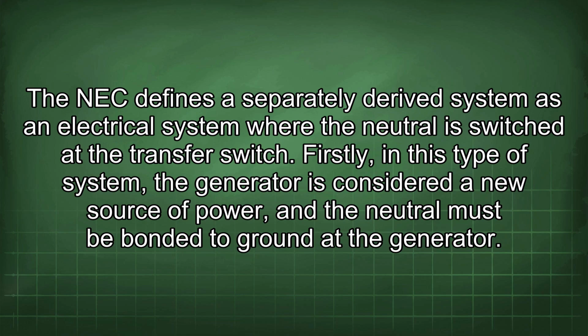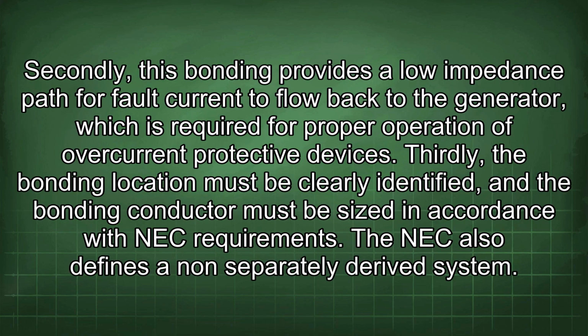The NEC defines a separately derived system as an electrical system where the neutral is switched at the transfer switch. Firstly, in this type of system, the generator is considered a new source of power, and the neutral must be bonded to ground at the generator. Secondly, this bonding provides a low impedance path for fault current to flow back to the generator, which is required for proper operation of overcurrent protective devices. Thirdly, the bonding location must be clearly identified, and the bonding conductor must be sized in accordance with NEC requirements.